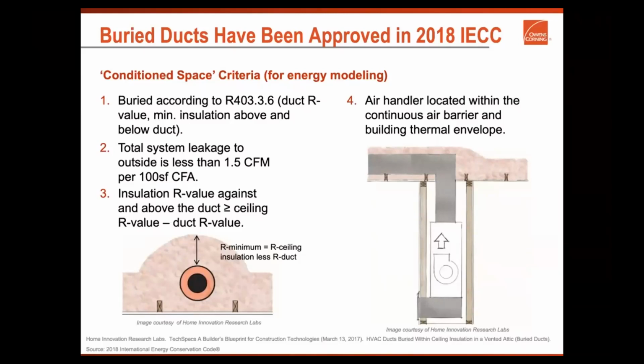And of course, I spoke about the air handler being in the envelope. While on paper that's great, I know in practice it's almost impossible. I worked with a builder trying to build what we ended up calling a doghouse in the attic, just to encapsulate the unit. And it's just a difficult process. So if the unit's not designed to be in the conditioned space, there is a way to do it in the attic now. But I don't know if the code language has been approved yet, so I'll probably have to get back to you on that.